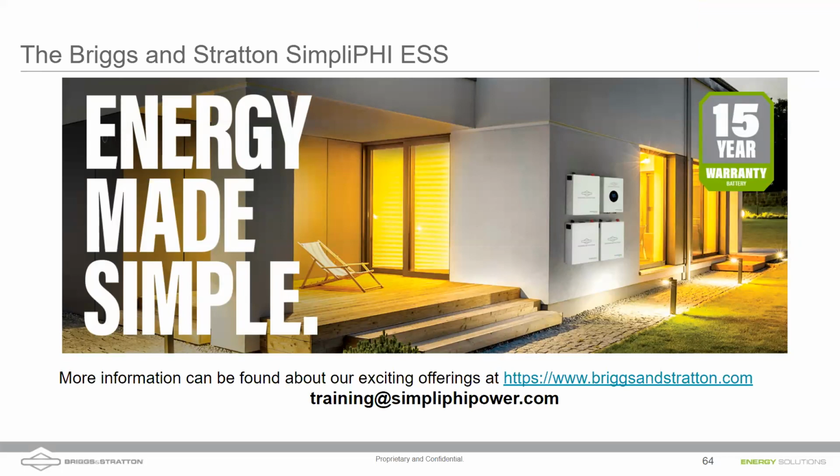And I will tell you this, that it's not a true transfer switch. A transfer switch is more in the generator, like break before make, and that's why in a lot of transfer switches you have to reset all of your clocks and your internet goes down and reboots. And a lot of these inverters, they're micro interconnection devices where the transfer time is so quick, like 8 milliseconds on our inverter, that a lot of times you're not even going to see the lights flicker. You're not going to have to reset your clocks, but they're treated a little bit differently in the code.